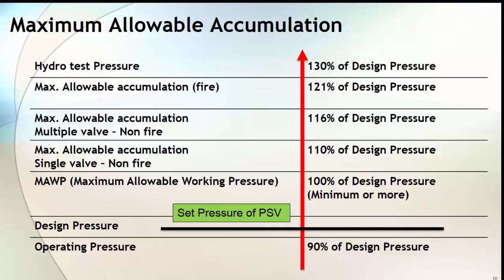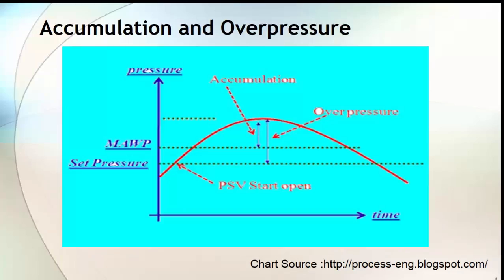The PSV is designed in such a way that it will not allow pressure buildup in the equipment beyond this limit. Let's go back to the previous chart to conclude what accumulation and overpressure are. The third dotted line shown in this chart is the maximum allowable accumulation, which depends on the code case — that means whether the equipment is fitted with a single PSV or multiple PSVs, or whether the equipment is fire type or non-fire type.